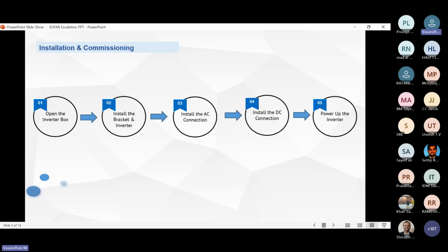We need to check it, and only after that do we install the inverter. If something is missing, like the bracket, it's usually not possible to miss it, but in some rare cases - about 0.1% - accessories might be missing. They will ask us to send it, and we can send it immediately from the Ahmedabad office. They can then install the inverter as per the user manual guidance, maintaining the top, bottom, and wall-to-ground clearance of 210 mm based on the inverter capacity model - that's available in the user manual.